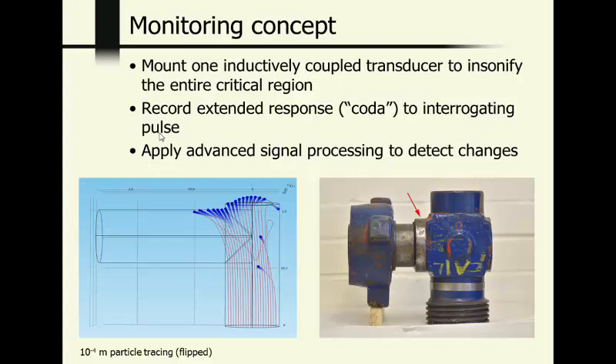What you're seeing over here is what the inside of that component looks like, and this shows the streamlines and the paths of some particles that are moving through this elbow, and those particles strike the surface in a number of places, particularly over here. And right underneath this thick area is where there's a substantial amount of erosion observed by looking at this failed component. And that's what we'd like to detect, the erosion which occurs underneath this thick-walled region.